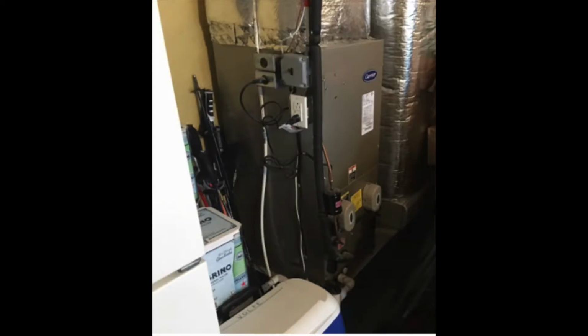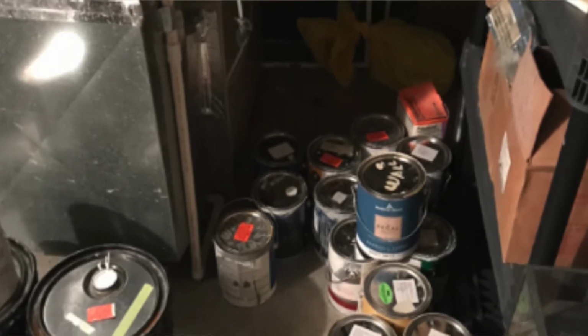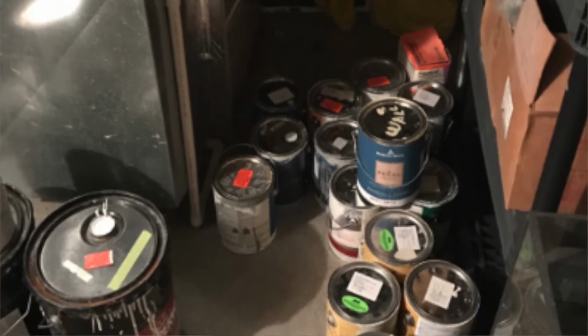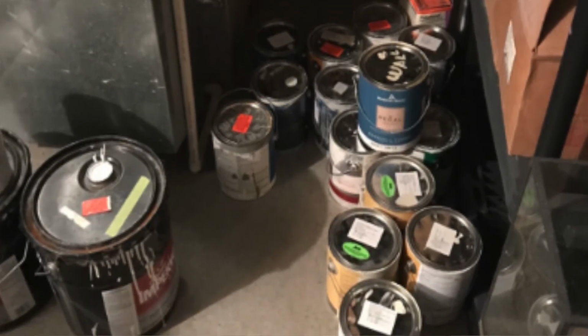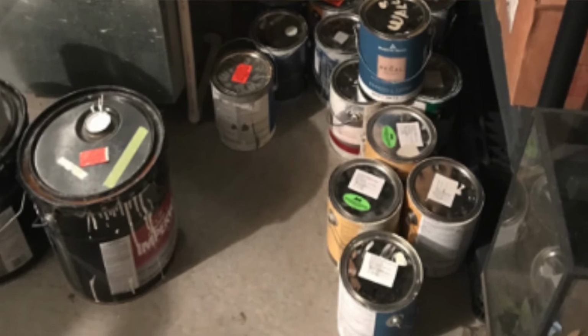One of the final areas I want to discuss for HVAC placement is within a garage area. It's really important that if you have an HVAC system in a garage, it has a separate closed door. It's really one of the worst places to place an HVAC system—you have car exhaust, a lot of times different paint cans. It's not a conditioned space, so it can cause a lot of condensation issues on the machine. So if you do have it located there, make sure you're keeping up on continuous maintenance with it as well.